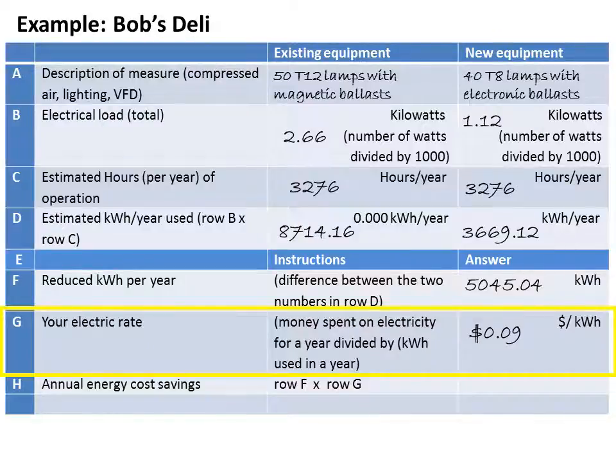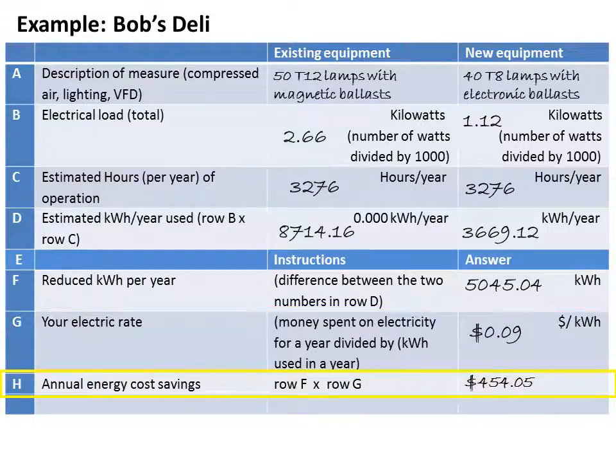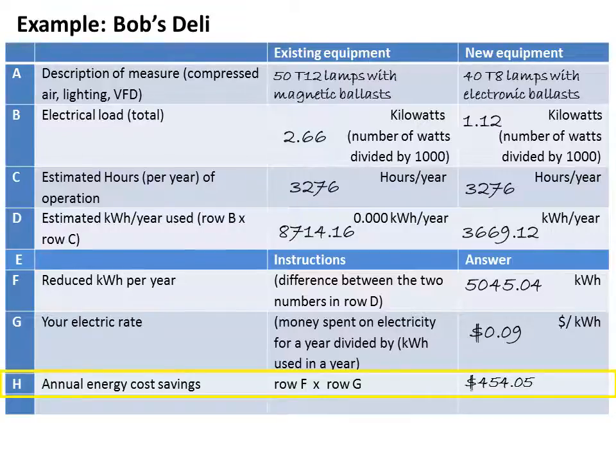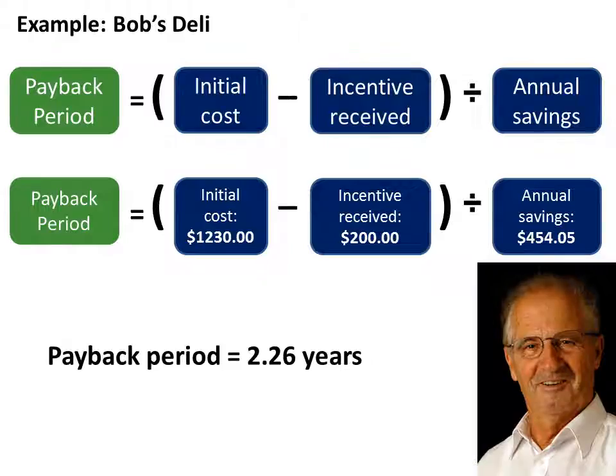Bob enters 9 cents per kilowatt hour as the electric rate on his annual savings worksheet. Now Bob multiplies the number of kilowatt hours he reduced per year in row F by his electric rate in row G. In Bob's case, this is 5,045.04 kilowatt hours times 9 cents, which equals savings of $454.05 every year. Then Bob plugs the numbers he's calculated into the payback period formula. Bob subtracts the incentive he will receive from the Act on Energy program from the initial cost of the project. Then he divides this number by the annual savings he calculated, and he sees that the payback period for his lighting project is 2.26 years.